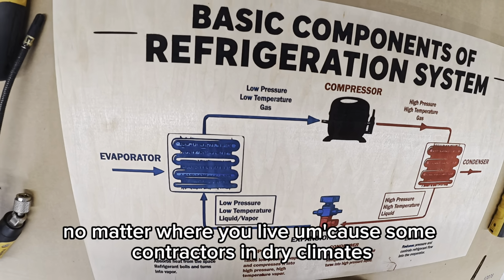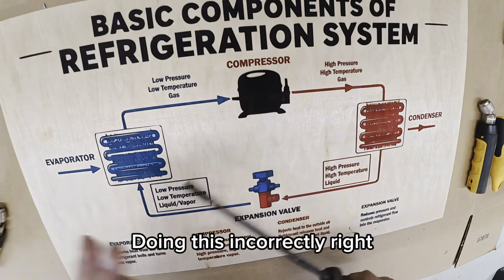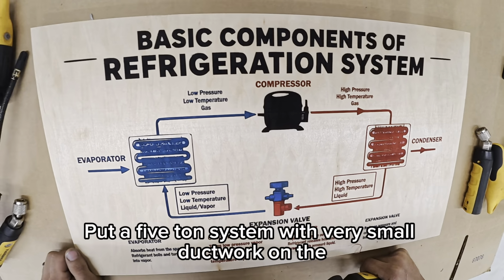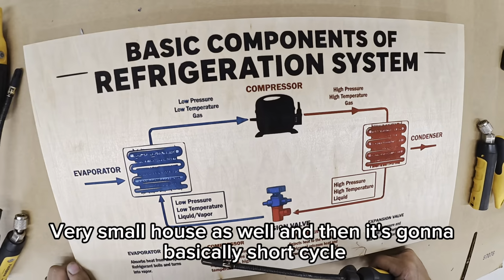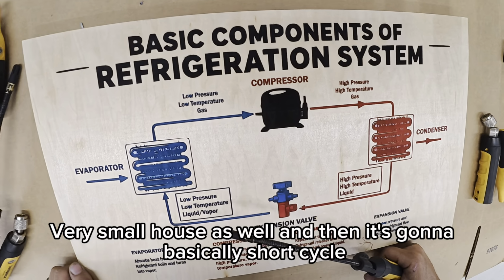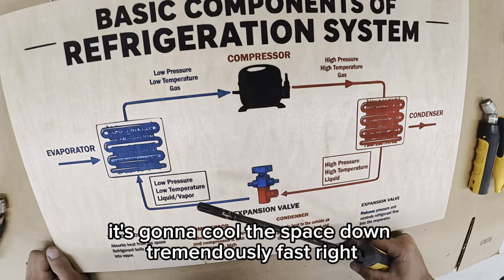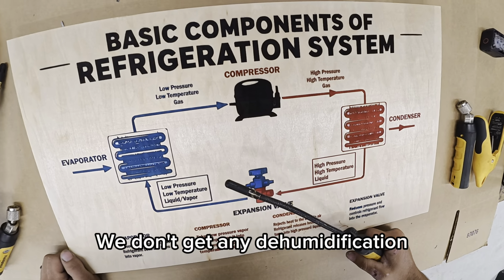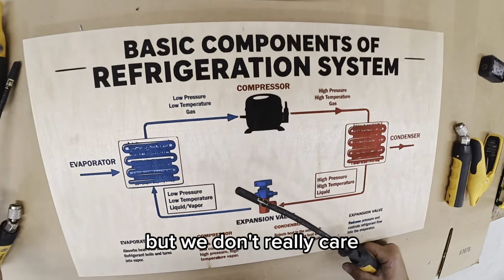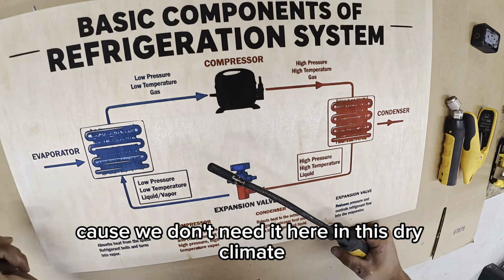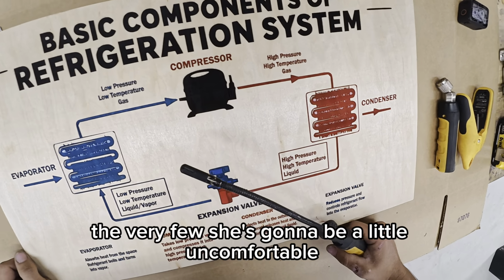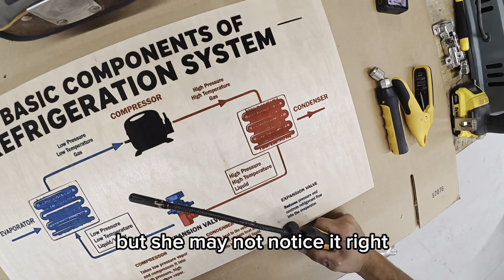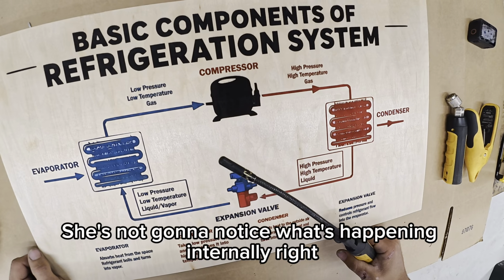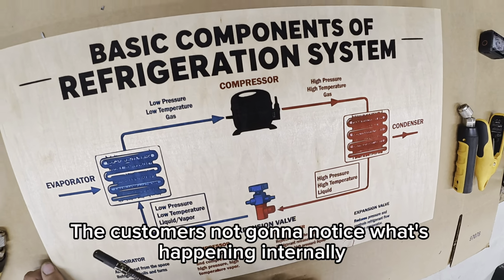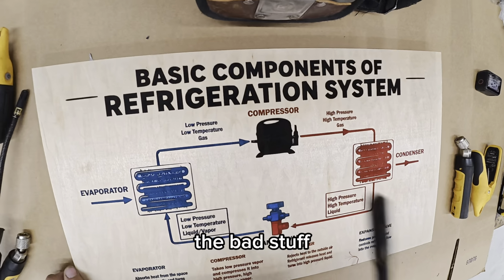Because some contractors in dry climates will get away with doing this incorrectly, right? They're gonna put a 5-ton system with very small ductwork on a very small house as well. And then it's gonna basically short cycle. It's gonna cool this space down tremendously fast, right? We don't get any dehumidification, but we don't really care because we don't need it here in this dry climate. But those days that we do need it, the very few, she's gonna be a little uncomfortable, but she may not notice it, right? But if she doesn't notice it, she's not gonna notice what's happening internally. The customer's not gonna notice what's happening internally, the bad stuff.